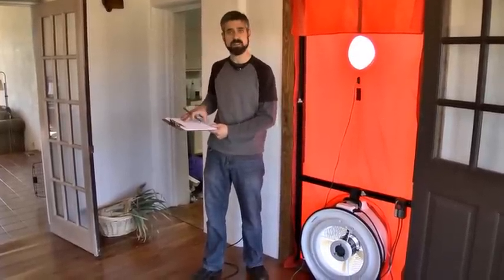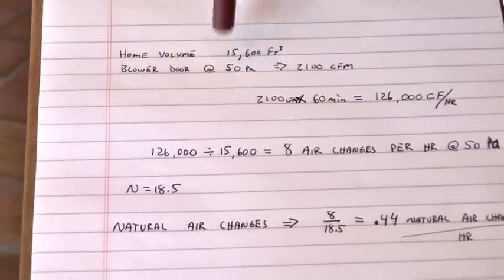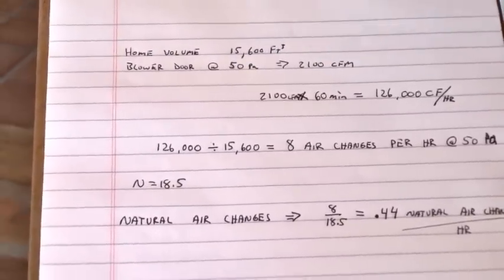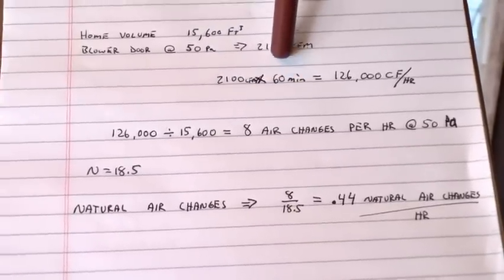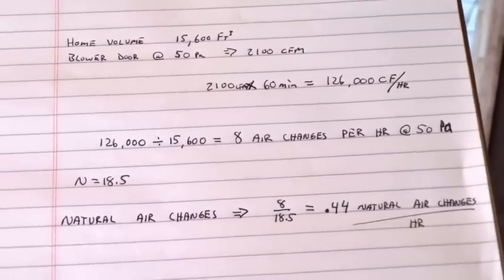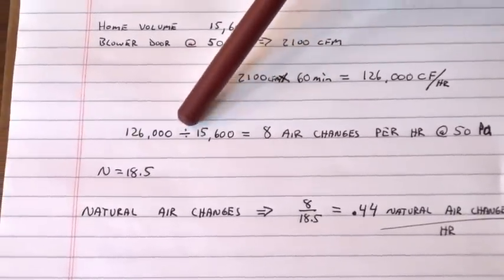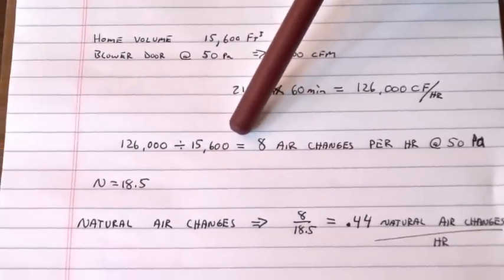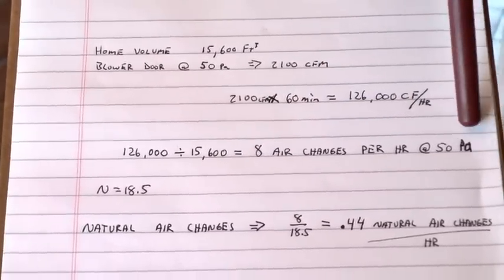Let's take a look at the numbers and see what we've got. Based on the measurements we took, we came out with a home volume of 15,600 cubic feet. With our blower door reading at 50 pascals, I called that about 2,100 CFM. 2,100 cubic feet per minute times 60 minutes gives us 126,000 cubic feet each hour. We take that and divide by the volume of our house, 15,600, and we're getting eight air changes per hour at 50 pascals.